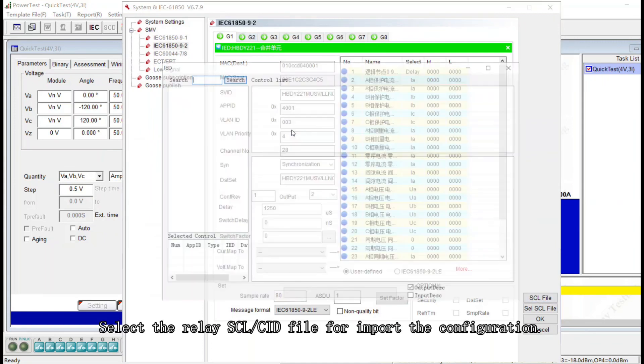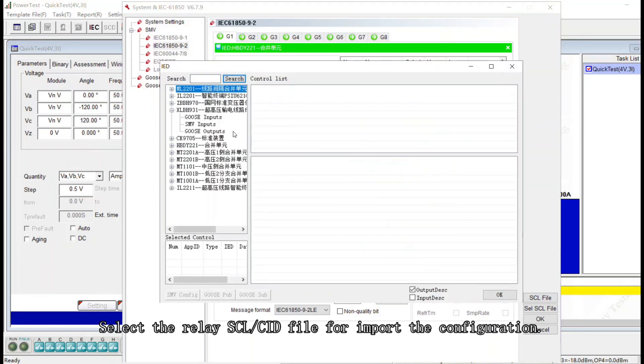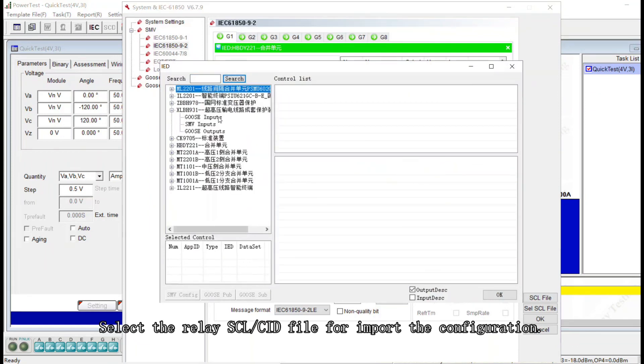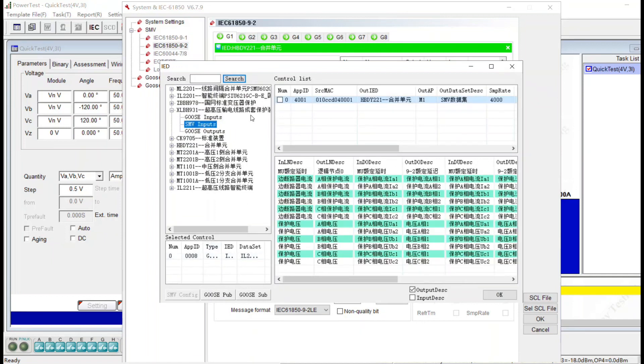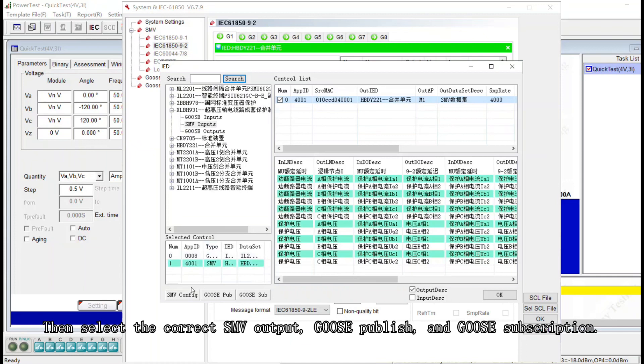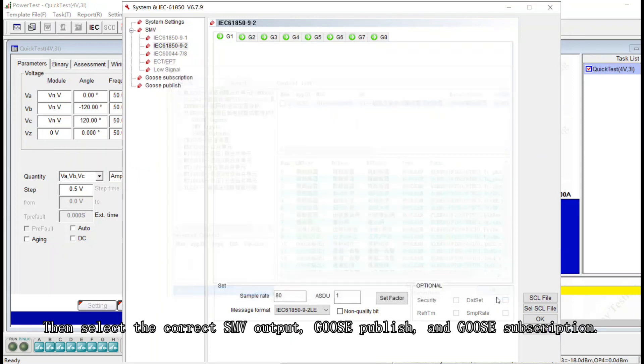Select the SCL file and open the CID file. Find the relay and Goose input, SMV input and subscribe it. After this, go to Goose output and subscribe it, then press OK.